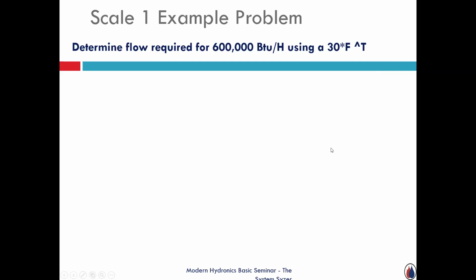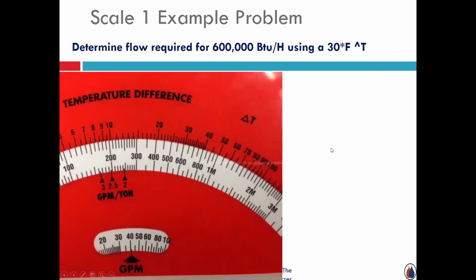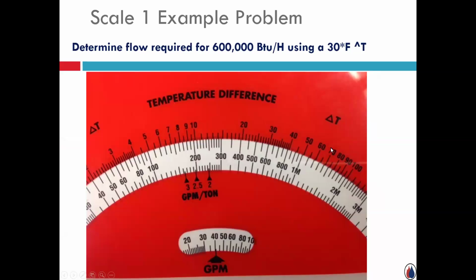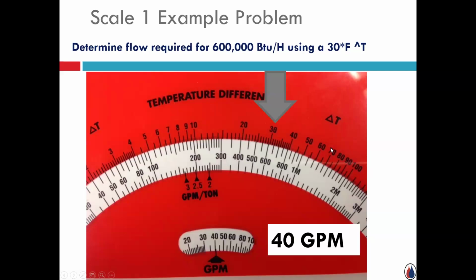One last quick one, a 600,000 BTU load at a 30-degree delta T. I don't know if I get into mentioning some applications, but we get involved with a lot of snow melting. It's one of the things that we specialize in here at FIA through a couple of our manufacturers. And so it's not uncommon to design a snow melt on a walkway, driveway, big parking lot, whatever, at a little higher, a little more liberal 30-degree delta T. So in this case, I'm saying I got a load, maybe it's a snow melt application, 600,000 BTUs, same thing, just line it up on that 30 and then just read, in this case, 40 gallons a minute. So 40 GPM will provide 600,000 BTUs if designed around that 30-degree temperature drop.